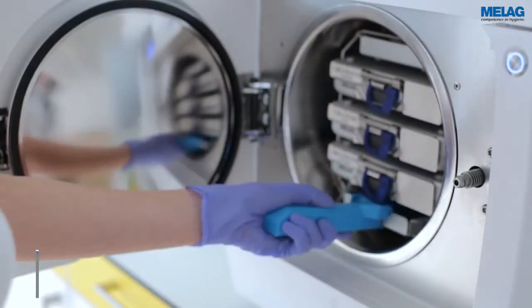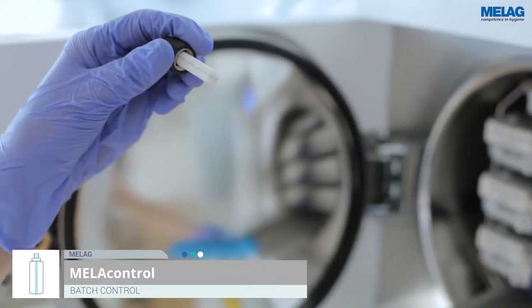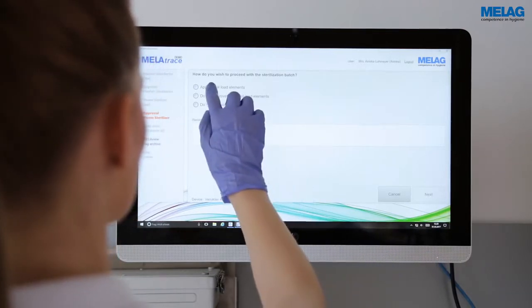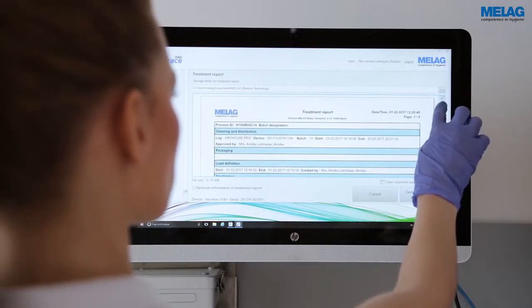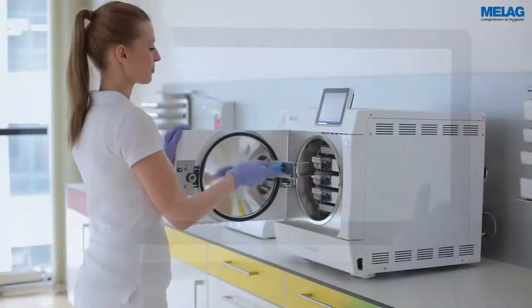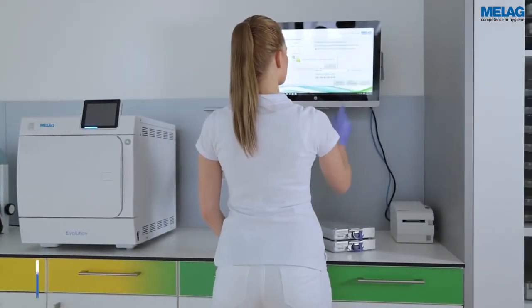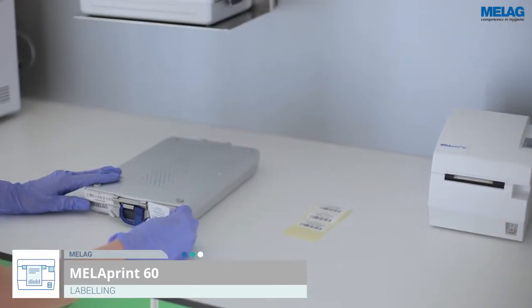Time saving and resource efficiency. The approval of the sterilisation procedure requires inspection of the MELAcontrol and the sterilised load. The entire process is then recorded in a legally compliant decontamination report provided by MELAtrace. After receiving the approval, the instruments are marked with a label. This label can be detected by a barcode scanner during treatment and assigned to an individual patient.